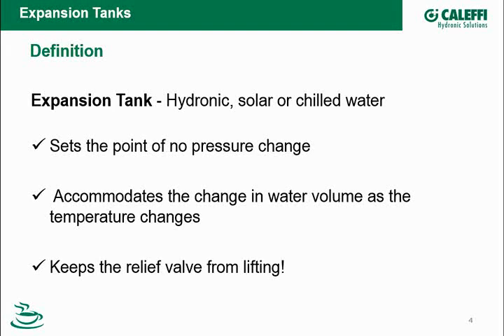As I heat up, the water expands and the volume becomes bigger. I need to put that water somewhere. As the system cools down, I need water to make up for the contraction. So in the hydronic system, I have water that will enter the tank, be held there, and then move back out as the system temperature changes. When somebody asks me about expansion tanks, I always jump down to the bottom one. A hydronic system should be a closed-loop system. Ultimately, the expansion tank is there to keep the relief valve from lifting. I need somewhere to put the expanded water.